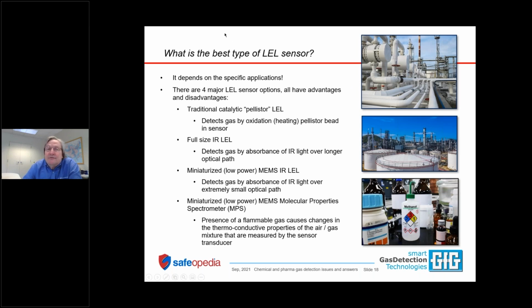Again, your choice of combustible sensor is really, really important, and which type of LEL sensor is best really does depend on what's going on. Traditional catalytic or Pellistor LEL sensors, the reason they call them Pellistor type sensors is the active bead. It looks like a little pellet that's made out of that alumina material that is then treated with the catalyst that allows the oxidation to occur. It detects gas by burning it basically in a controlled catalytic way on and in that bead, which heats that bead up to a higher temperature than it started out. So how you register the concentration of gas is by how much that bead is heated up beyond the temperature that it started out at.